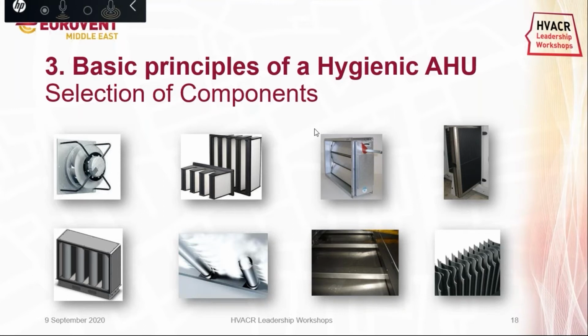Filters for the first and second filtration stages, DIN norm also asks for ePM1 60% for the first filtration stage and 85% for the last filtration stage, previously known as F7 and F9, as a minimum class. Dampers, according to EN 1751, minimum class 2 dampers are required, whereas for higher hygiene requirements, it should be class 4. There are many more requirements for the coils, sound attenuators, humidifiers, and so on, which basically depend on the same principles explained before about the materials, corrosion resistance, cleanability of the design, and so on.